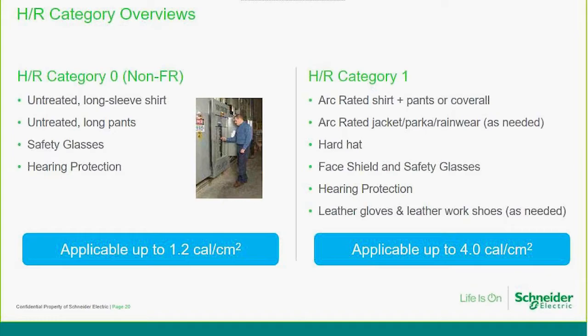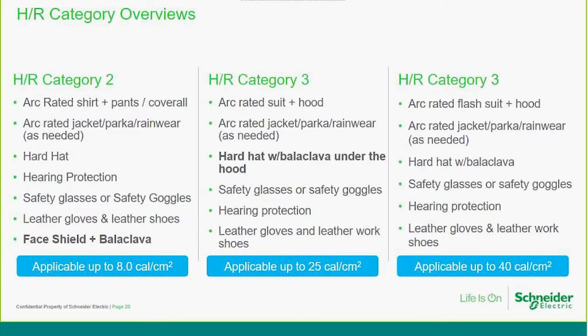Category 1, we start to go up a bit more, so we're now at 4 cals per square centimetre. These are recommendations of the PPE experts in our industry. We talk about a proper shirt or a jacket, a hard hat, a face shield and safety glasses, some hearing protection, and leather gloves and leather work shoes. So straight away we can see we've gone from something that is probably everyday clothing, with some basic safety glasses and hearing protection, to something a little bit more specialized. As we go up further, we get into face shields and balaclavas.